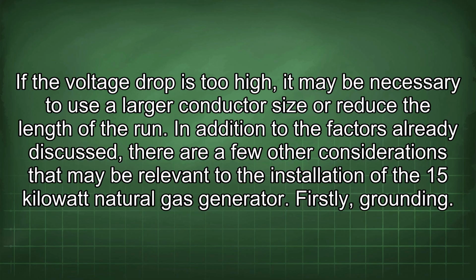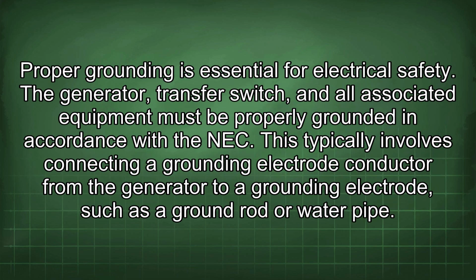length of the run. In addition to the factors already discussed, there are a few other considerations that may be relevant to the installation of the 15 kilowatt natural gas generator. Firstly, grounding. Proper grounding is essential for electrical safety. The generator, transfer switch, and all associated equipment must be properly grounded in accordance with the NEC.